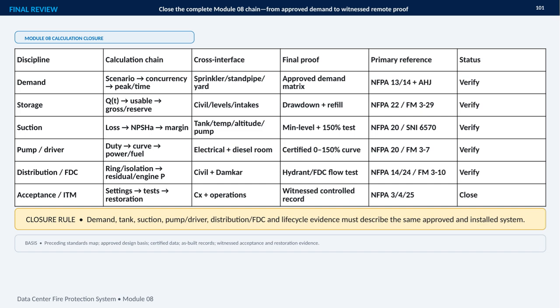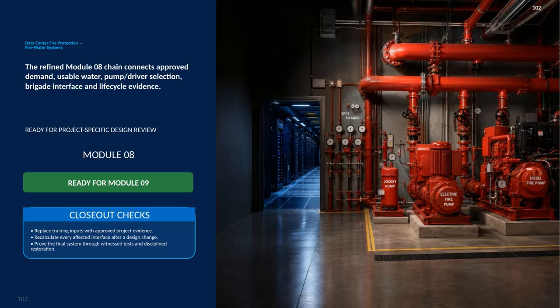Distribution and the FDC complete the hydraulic path through ring configuration, isolation, residual pressure, and flow testing. The final discipline is acceptance and ITM, including settings, testing, restoration, commissioning, and operations evidence. Closure means these interfaces are consistent, certified as built, approved, and witnessed. The primary references include NFPA, FM, SNI, and AHJ requirements. Most rows remain marked Verify, while acceptance and ITM is marked Close, so the remaining task is disciplined evidence confirmation, not another redesign. This module closes the chain for data center fire water systems, from approved demand and usable water through pump and driver selection, brigade interface, and lifecycle evidence.